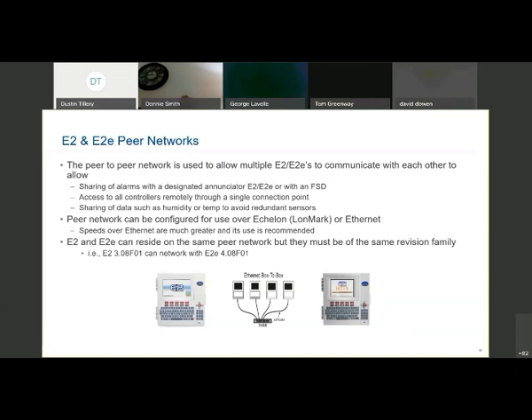The important thing to note here on this peer network is your firmware. The firmware of the controllers must match. So if you have an old E2 that has the 3.08F01 firmware, it will communicate to the new E2s on the peer network, provided that the firmware numbers are the same. As you can see in this example, the 3.08F01 would be the same equivalent firmware for the E2e as the 4.08F01.